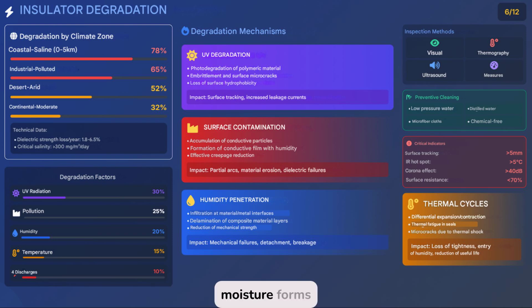Surface contamination with moisture forms conductive films that cause partial arcing and erosion. Detecting these failures in a timely manner requires predictive inspection, visual, thermographic, ultrasound, and dielectric measurements. Preventive cleaning with distilled water and no harsh chemicals is essential to preserve the insulator's integrity. Indicators such as tracking greater than 5 mm, hotspots greater than 5 degrees, corona effect greater than 40 decibels, and surface resistance less than 70% alert to critical conditions.